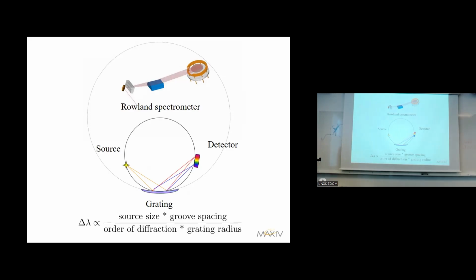So the further you can pull them apart, the easier it is to detect. And to note, this is assuming you have an infinite resolution in your detector, of course, because the detector will start limiting you fairly soon. But these are the parameters that we can play with. And then you can maybe understand why the RIXS instruments are so big. Because the magic button of groove spacing really kills your performance above 2000 lines per millimeter or so, then it gets a struggle to measure.